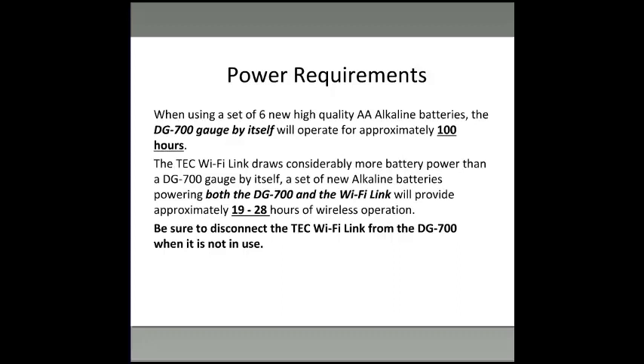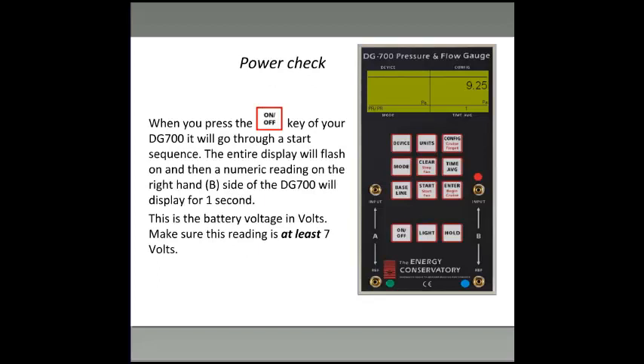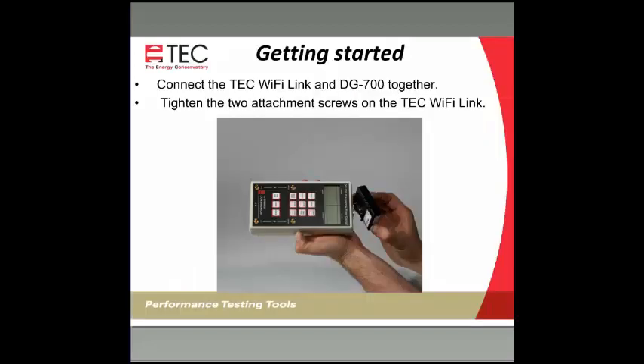The Wi-Fi link is really going to pull down battery life. There's also a power check feature on all DG700s that a lot of people aren't aware of. Every time you power up a DG700, it goes through a startup mode - every light on the display pops on for a second, and then in channel B, where you normally see flow, it flashes the voltage. If you do this voltage check with no Wi-Fi link on, you'll get a reading, but the minute you power it up with the Wi-Fi link on, it's going to start pulling volts. You want at least 7 volts to get through your test - if not, find some fresh batteries.